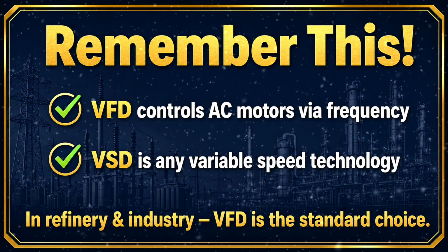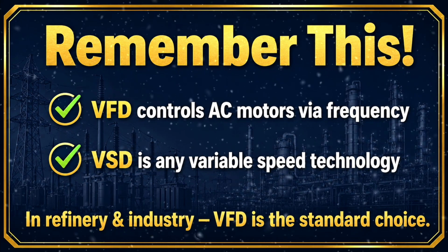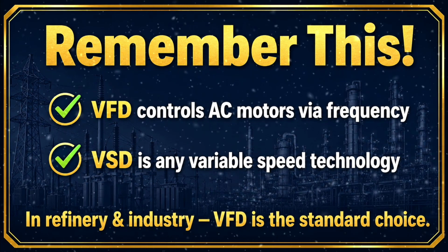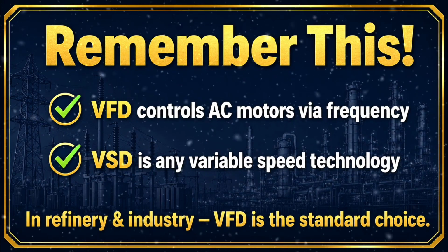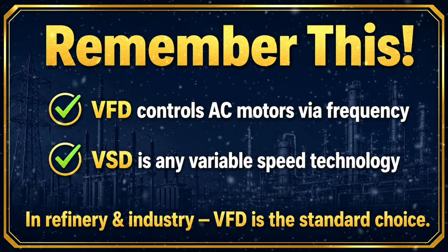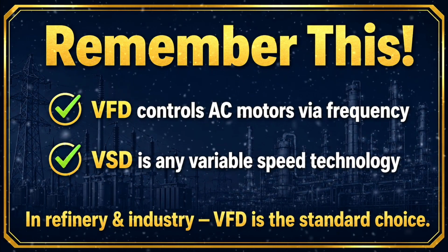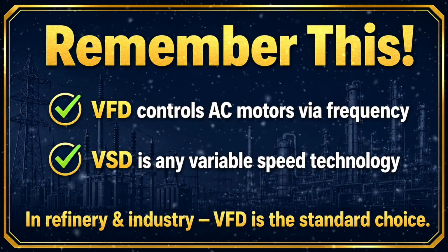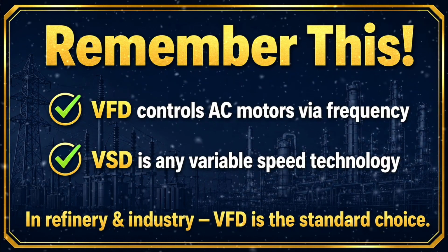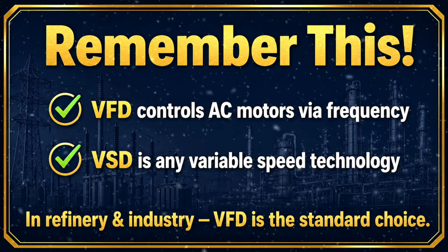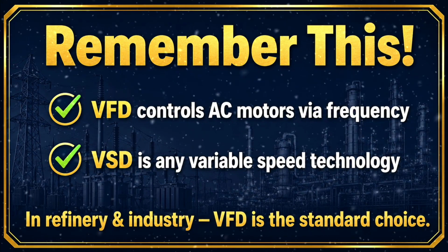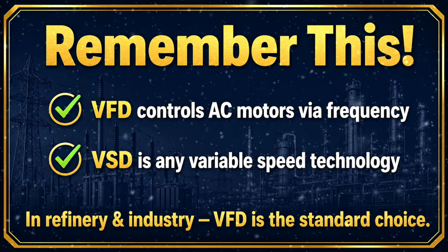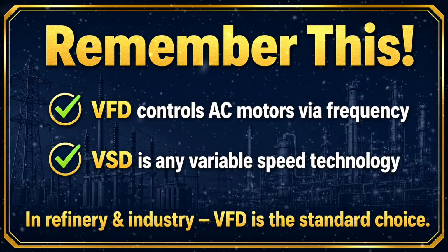Benefit 2. Reduced mechanical stress. DOL starting creates an inrush current of 6 to 8 times full load current, causing severe mechanical shock to motor windings, shaft, couplings, and gearboxes. VFD soft start eliminates this completely. Motor ramps up from 0 Hz to 50 Hz over a programmed acceleration time.